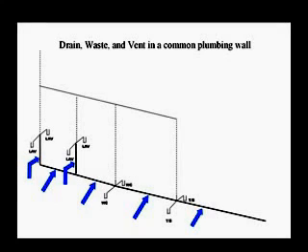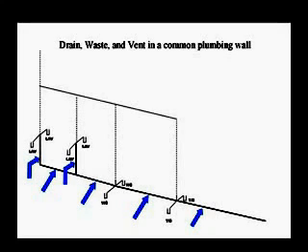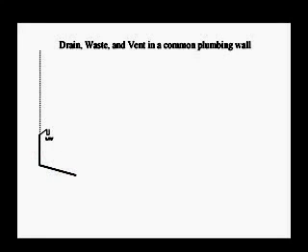To become familiar with the sizing procedure, let's determine the horizontal and vertical drain pipe sizes for this drainage system. Let's start with one lavatory. Refer to the drainage fixture unit values table 7-3 and find a single lavatory in a private individual dwelling has a value of one fixture unit.